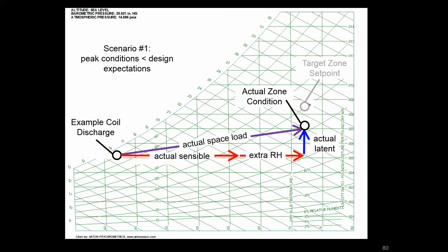When the zone isn't providing that load, that means that you're cooling to a condition if you have a constant coil discharge set point. You're cooling to a condition such that you're going to need more reheat because the zone isn't providing that load. The zone isn't doing any of its own reheat. Something like a reheat coil is going to naturally take up more of that. And that's not a condition that an occupant is going to notice, or your O&M team. The HVAC system is doing its job, but it's using more reheat than may have been expected, at least for design conditions.